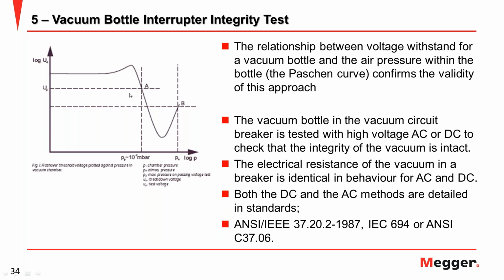So because this is low, we can use the second way to detect the pressure problem with the vacuum bottle test, the voltage withstand test. And actually you can test with AC or DC, it doesn't matter. But the DC has an advantage because the magnitude of the current is lower than the AC. So with DC it will be safer for testing the vacuum bottle.